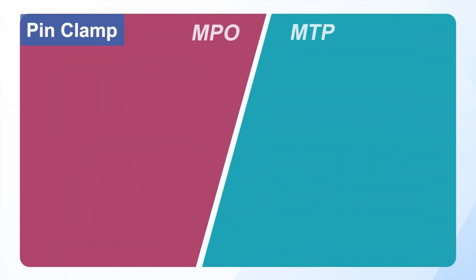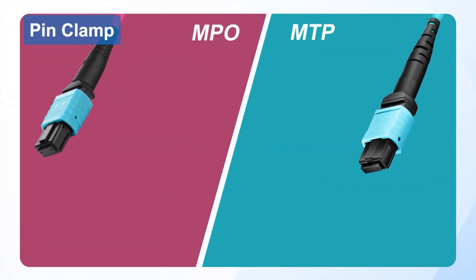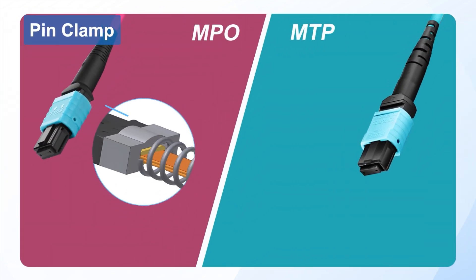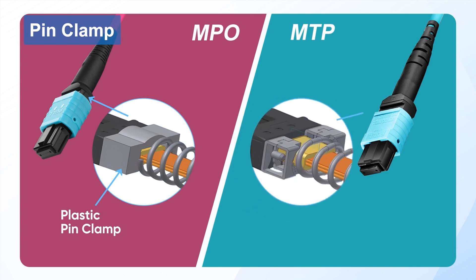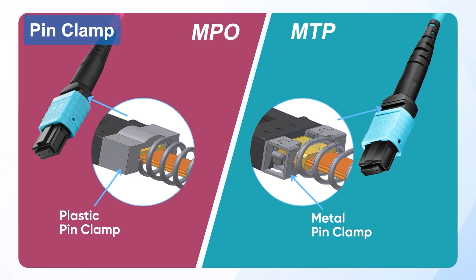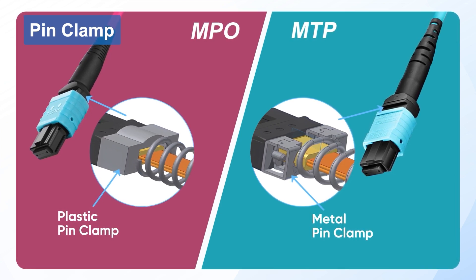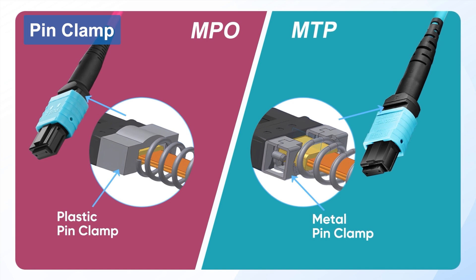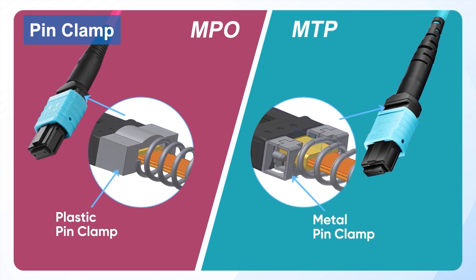Additionally, the pin clamp is also different. MPO connectors typically use plastic pin clamps that break easily during frequent mating cycles. In contrast, MTP connectors employ durable metal pin clamps, reducing breakage risk. They also feature elliptical springs that maximize clearance between the fiber ribbon and spring, protecting the ribbon during insertion.